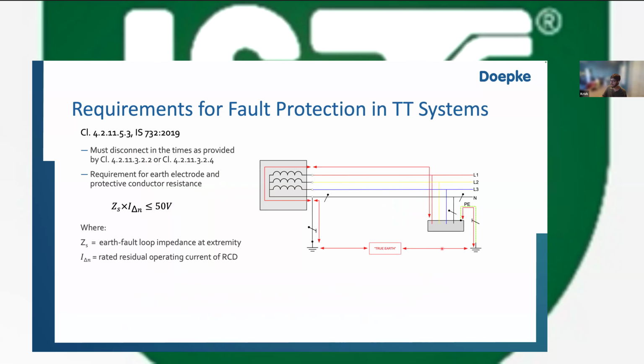The other way of looking at it is that instead of just considering the resistance of the earth electrode, you can also consider the overall loop impedance because that gives you a fuller picture. The sum of this entire impedance times the rating of the RCD has to be 50 volts or less, right? So again, disconnection times are, as I mentioned previously, given in IS 732, but generally for an elevator, 1 second is the applicable time.